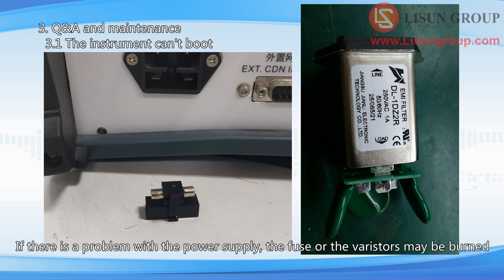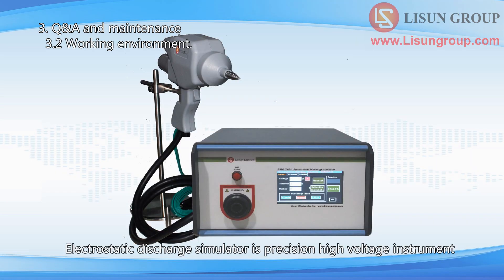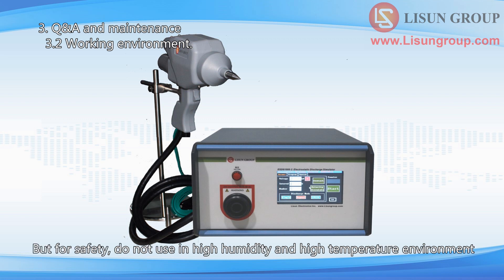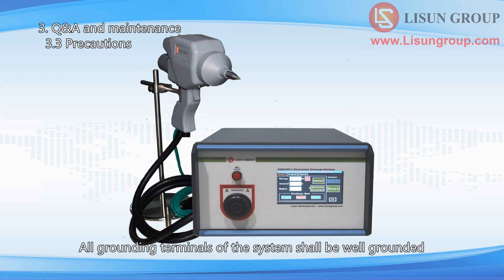If there is a problem with the power supply, the fuse or the varistors may be burned. Please ensure the stability of the power supply of the instrument. If necessary, you can buy Lisun's regulated AC power supply. The electrostatic discharge simulator is a precision high voltage instrument. Do not use it in high humidity or high temperature environments. The working environment is: relative humidity 30% to 60%, temperature 10°C to 35°C, atmospheric pressure 86 to 106 kPa. All grounding terminals of the system shall be well grounded. Do not touch the electrode of the ESD gun with your hand after the instrument is powered on, to prevent electric shock.